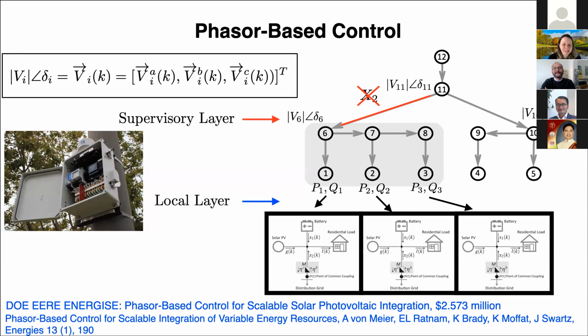So if our voltage phasors were the same, we would have no power flow at all across that line. We've created a virtual switch essentially for our grid, and so that gray shaded box could be considered a microgrid within a larger grid that could switch in and out without a physical switch.